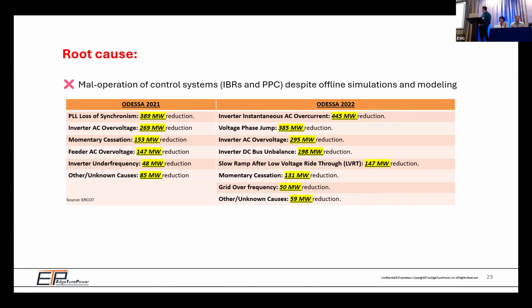And if you look at the table here, we have PLL loss of synchronism, which is a highly nonlinear behavior. We have inverter AC overvoltage. We have momentary cessation. Because of time limitation, I'm not going to go through all the details. But these are events that cannot be properly captured in PSCAD. And that is why we want to gradually go to hardware in the loop testing, why hardware in the loop testing can be very, very helpful here.